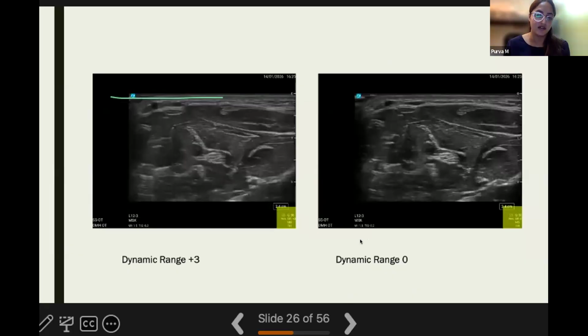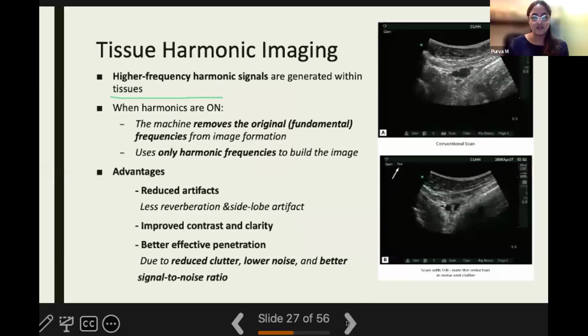This is an image of the median nerve that we took in our ultrasound, and we set the dynamic range to +3 because the Philips Sonosite allows us to set it in ranges of 0, 1, 2, and 3. That is the maximum dynamic range that our ultrasound allows us to have. And then we see this very smooth image. While on the other side, when we have the dynamic range set to 0, we see a slightly gritty, high contrast image, but smoother lines and extremely bright.